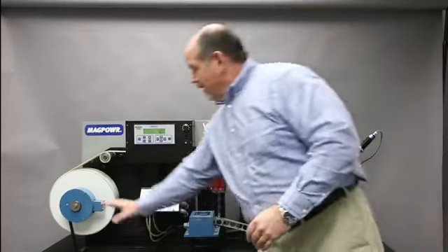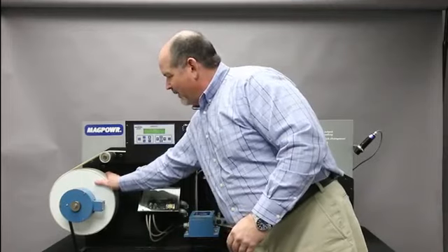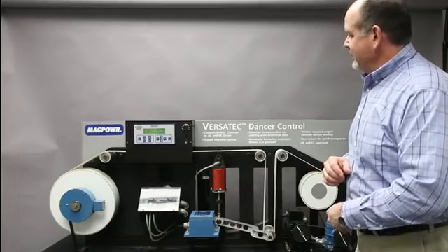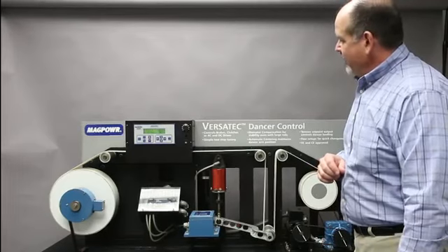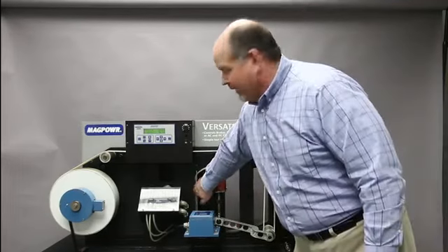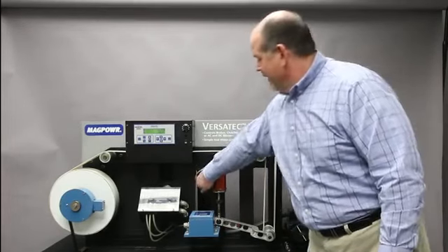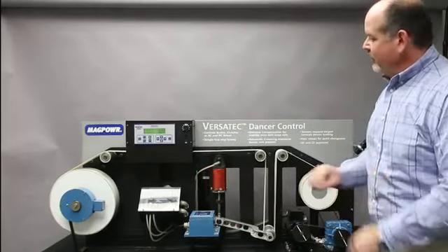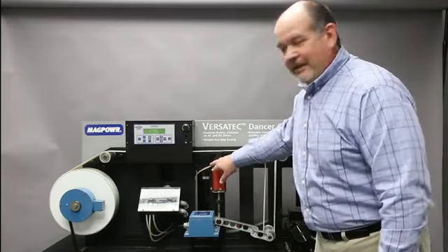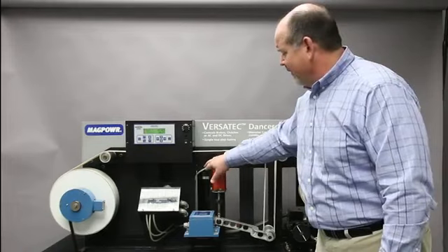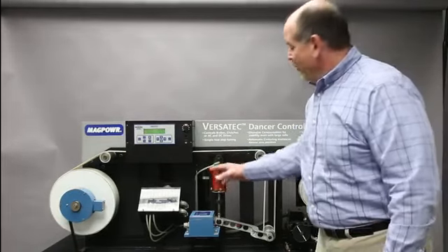Another thing we have on here, this is static back here, but we did include a magnetic particle brake, which would be included on the system. And the last component that I really want to look at is this air cylinder. There's not an air cylinder, but a tank, a reservoir that's on the back side here. That's very critical, because if you look at the air line going to the cylinder, it's typically going to be a smaller diameter, and the longer that run is, the more of a lag.